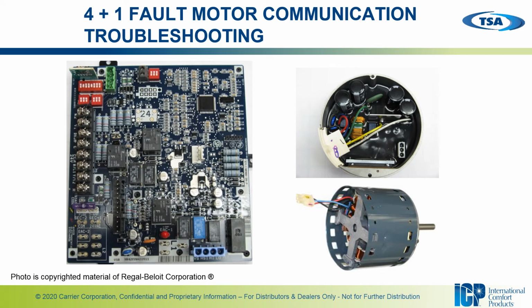And now we get to the motor troubleshooting. All right, if you received the 4+1 fault in the self-diagnostic check, that's going to indicate a motor issue. Like I said before, it could be a connection issue between the control board and the motor, but if there is no connection issue, you can separate the module from the motor and do a couple of quick tests to tell which is faulty.